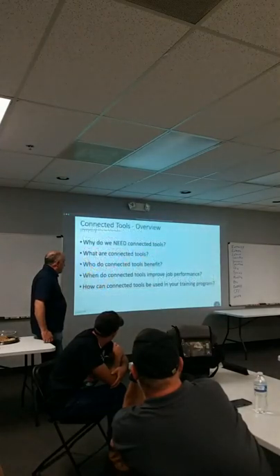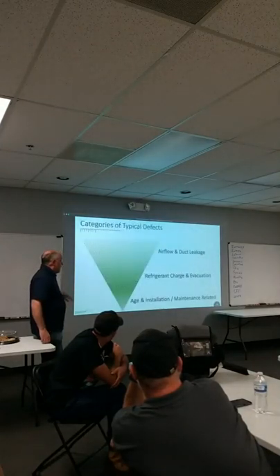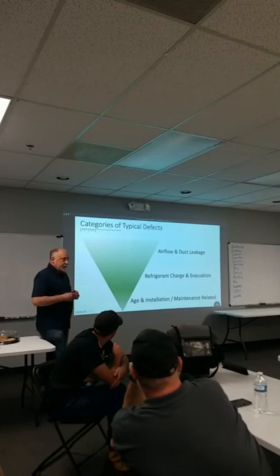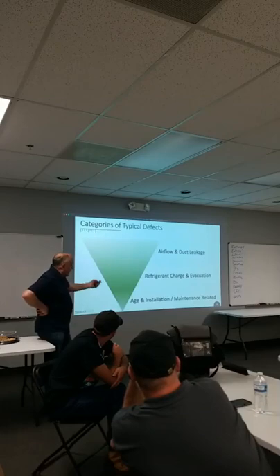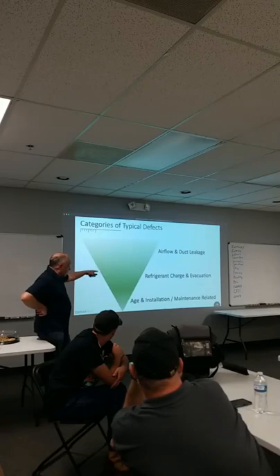All right. So when you're talking to industry today, I think a lot of us don't realize it, but the biggest problems we have are airflow and duct leakage, followed by refrigerant charge and improper evacuation. And the last ones are actually installation and maintenance related issues. Airflow and duct leakage are two of the biggest problems we have in the industry. There have been several studies done.